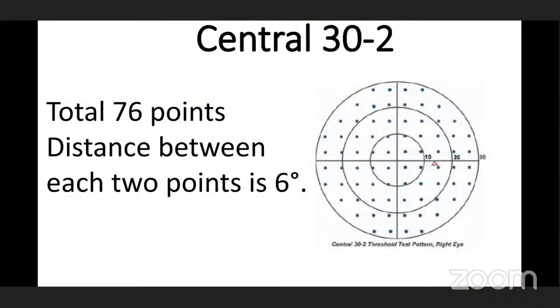Central 30-2: '30' refers to 30 degrees of visual field area from center, and '2' is the offset from the horizontal and vertical meridian. There are a total of 76 points, with a distance of 6 degrees between each point. It is used to test the central area.